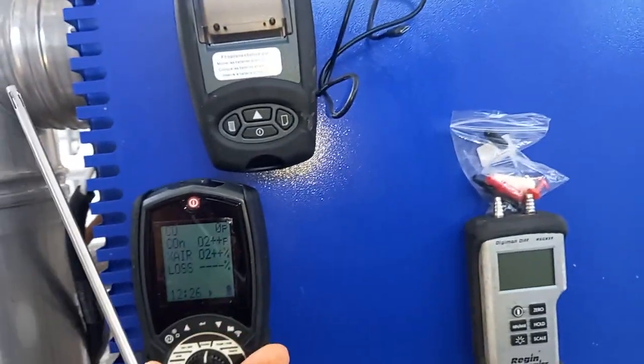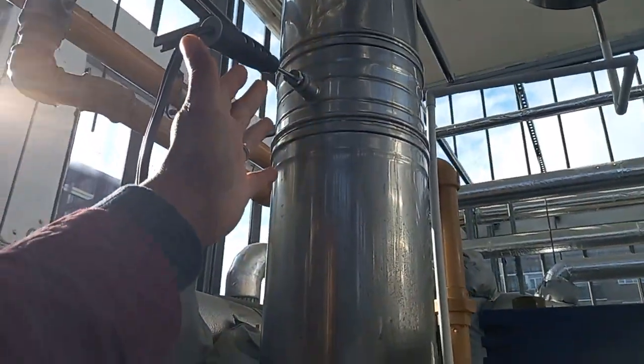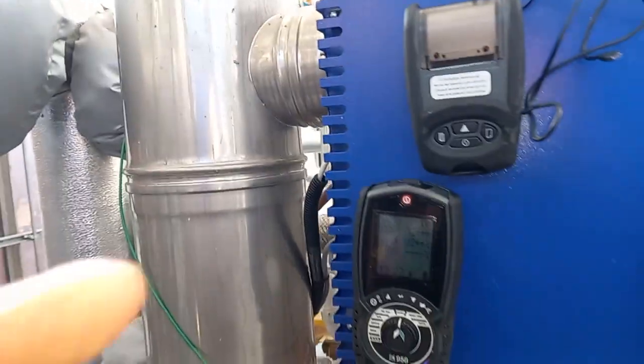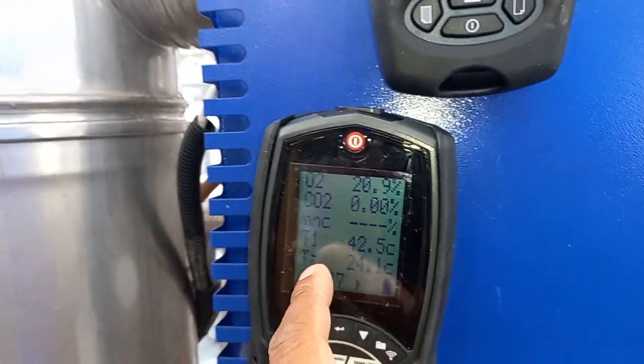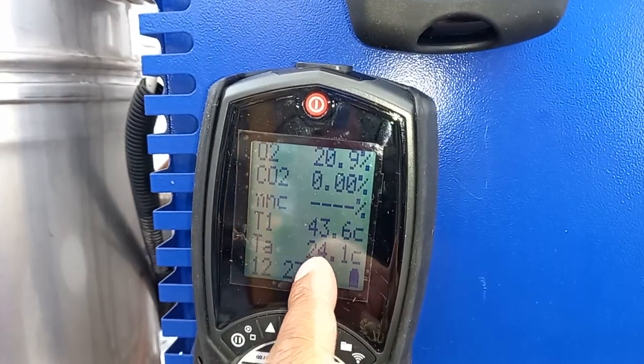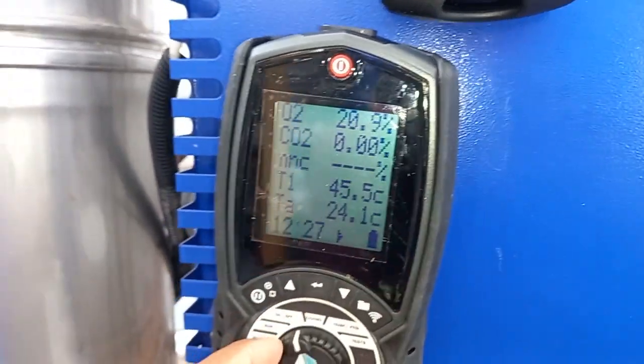Okay, this scenario I'm testing here on the boiler. You know on these boilers there is another test point inside, but I'm not going to get the case off at this particular moment. This is just for the video. So we're checking the temperature of the flue here. Here's the flue temperature rising.